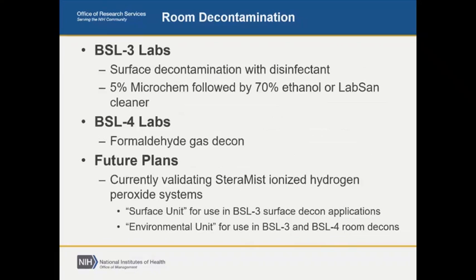And finally, our BSL-3 and BSL-4 room decontamination procedures. For BSL-3, we use surface decontamination with disinfectant, and that currently for SARS-CoV-2 for us is 5% Microchem, and they follow that with either 70% ethanol or a dilution of LabSan cleaner to remove the sticky residue that exists after the Microchem. And then for BSL-4 labs, we use our standard formaldehyde gas decon procedure.